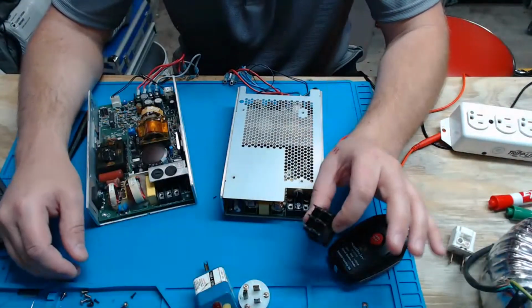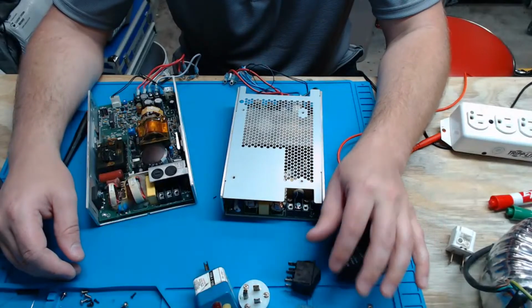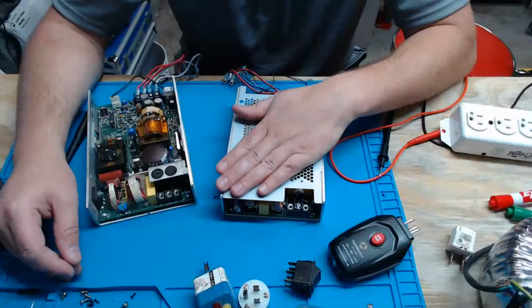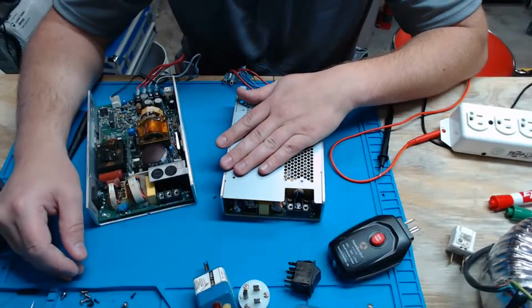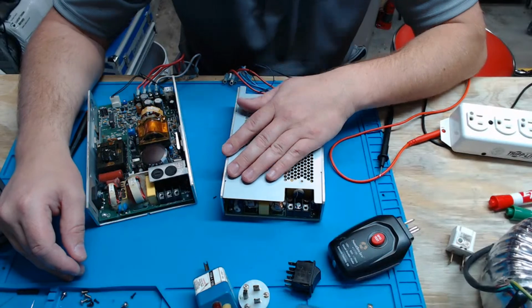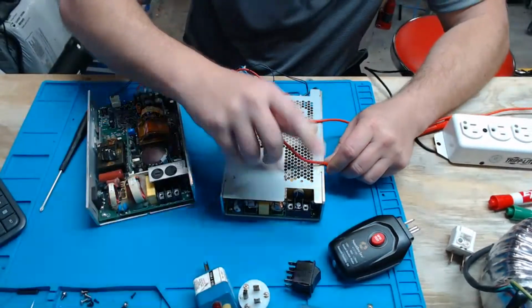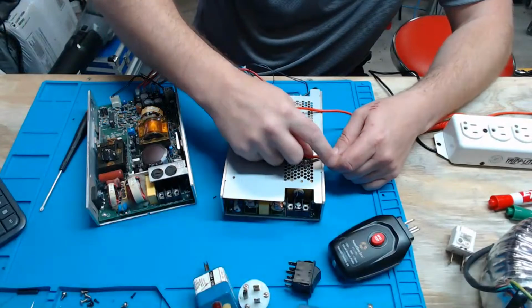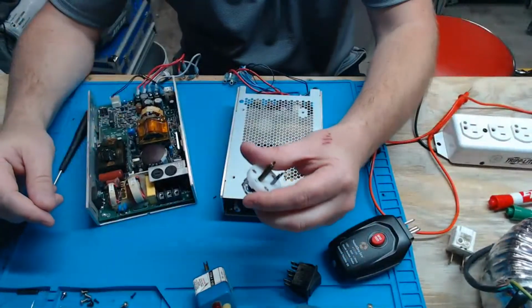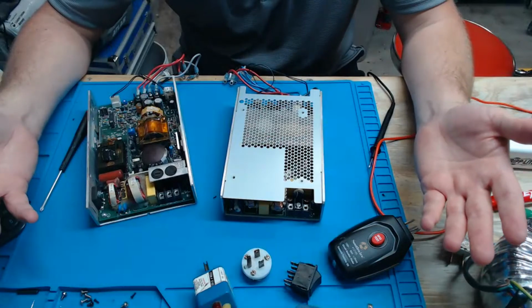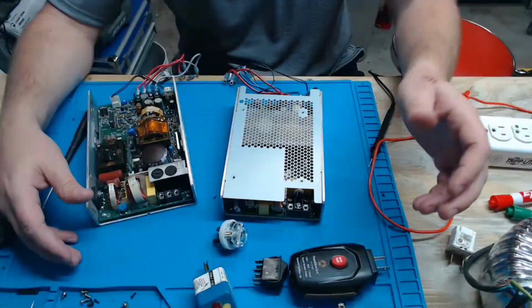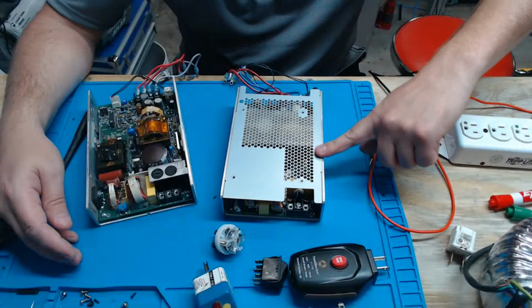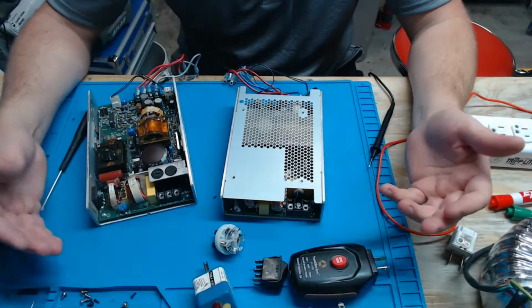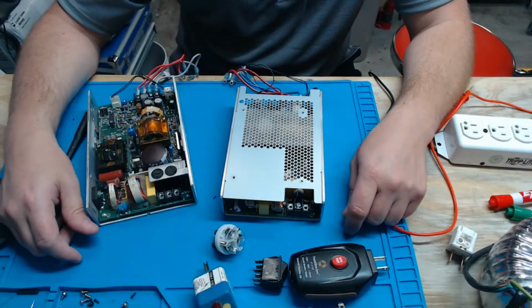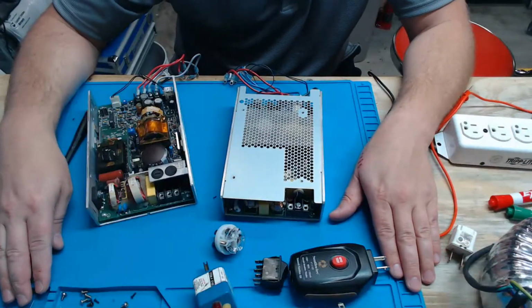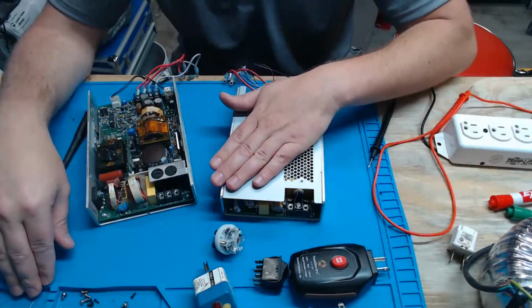And never ever assume that something is wired correctly. If it's plugged in, always assume that every metal surface is hot, okay? Because you never know if there's a wire in there that got pinched, which I have seen so many times. If there's a wire in there that's pinched and you have a really poor ground, that happens all the time on medical equipment. We abuse stuff like it's going out of style. If you have a really bad ground and a pinched cord, well, guess what? Your entire chassis could be hot. It could be, and in fact, probably is. So always assume that something is hot and live.